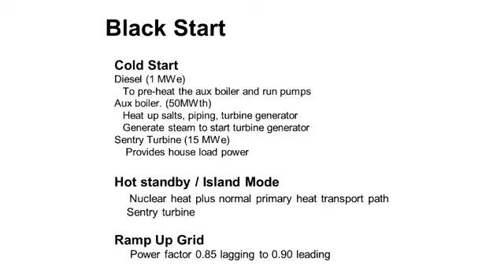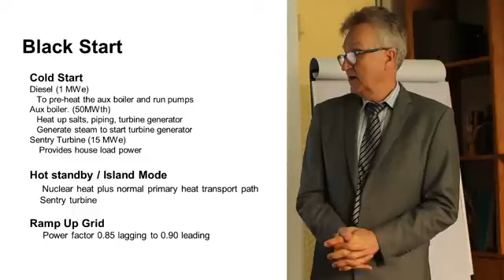We use the Sentry turbine to use that steam to generate 15 megawatts electric. That provides house load power so it can start pumping salts and seawater and such around. We can then transition to hot standby or island mode, where we would use normal nuclear heat and come down the primary heat transport path to the Sentry turbine. All of this would be covered by the nuclear side, and then we'd pick up with the Sentry turbine. And we can sit in that mode for days, years even.